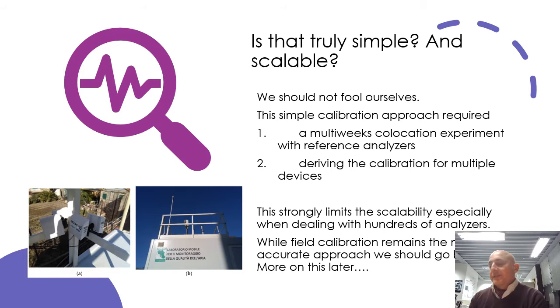This is what the original field calibration approach is all about. You have to collocate all your sensor devices with a reference analyzer. You observe and record the responses across all the collocation times, which has to span an adequate amount of time that is sufficient to show different weather conditions, different conditions of the pollutant fingerprints, so different anthropogenic conditions and so on.